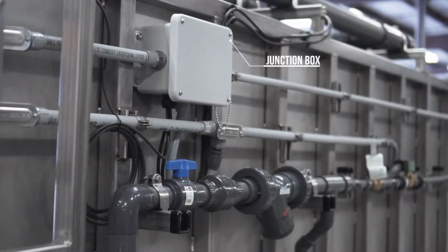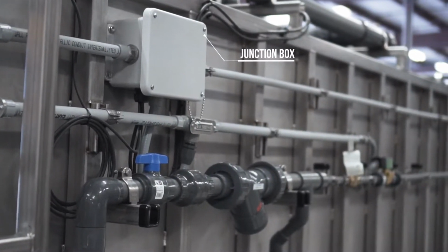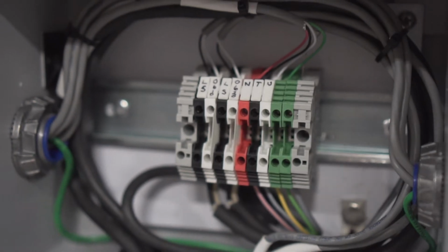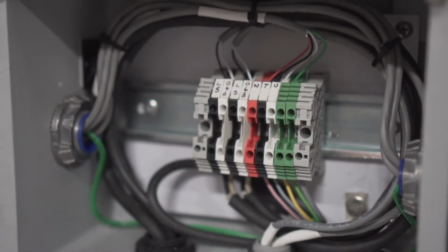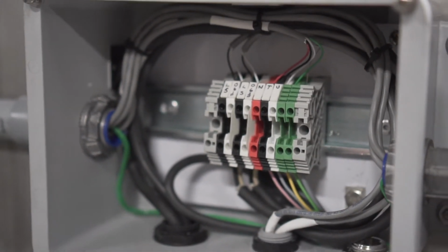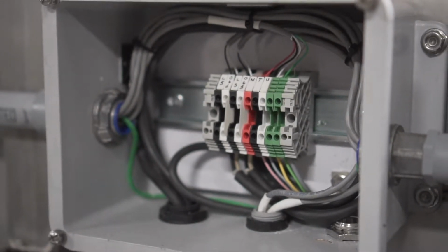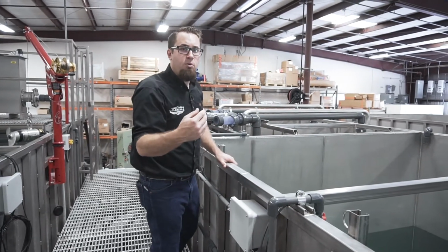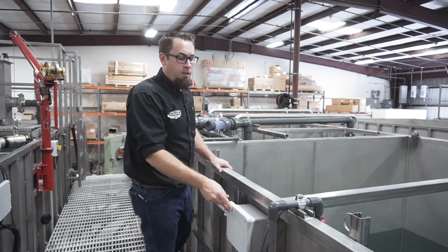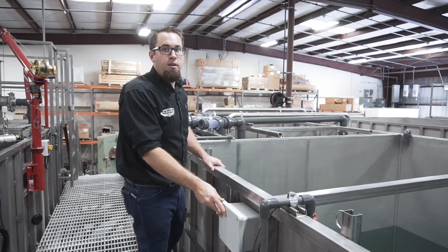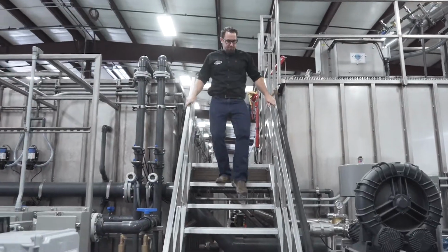There are junction boxes near all of the pieces of sensory equipment, so in the event that you have a failure of an actual probe itself, you can come back to a junction box that's usually feet away from the actual slide rail system, disconnect there, pull your piece of equipment, install the new piece of equipment, and then make determinations right then and there. You don't have to pull wire all the way back to the MCC.